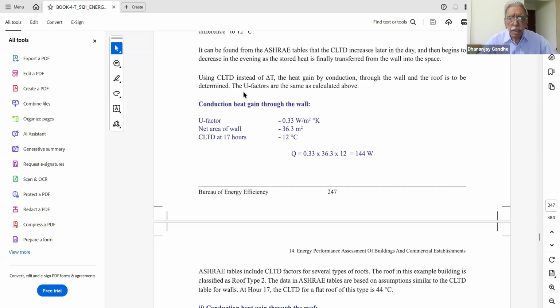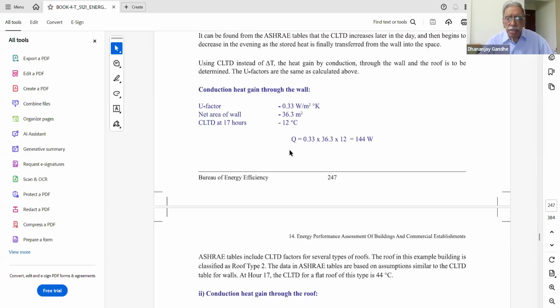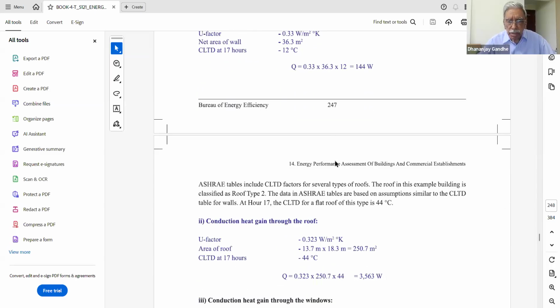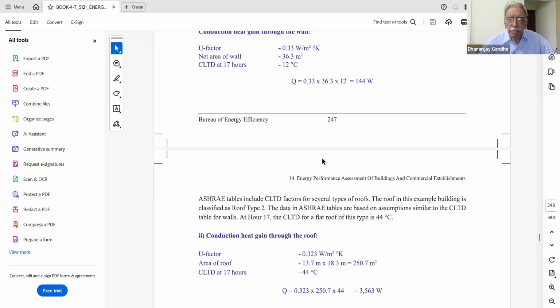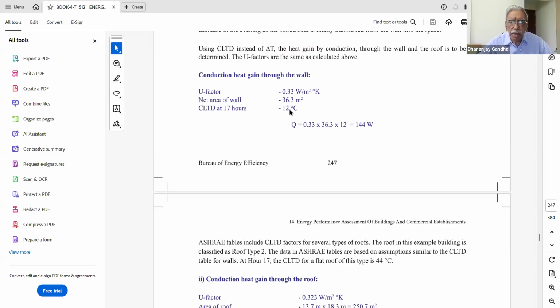because the temperature conditions vary over the period of time. So we need to calculate the average temperatures outside. So the CLTD factor is to be used. The CLTD factor for 17 hours is to be taken as 12 degrees centigrade as per the standard norm. Although the actual temperature difference may be small, for the purpose of calculation of cooling load, we have to take this as 12 degrees centigrade.